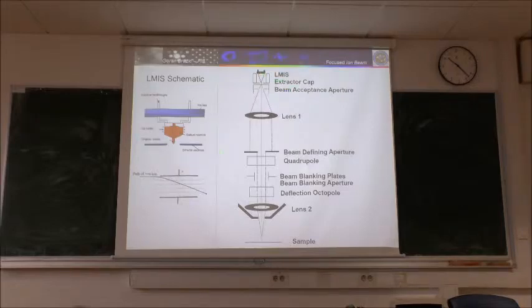this extractor cap. So you extract the ions from that tip. You have a first lens, you have an aperture, you have some quadrupoles and octopoles here. I will explain later on why we do need them. Some blanking plates so that we can blank the beam. We do not want to have a beam, we just blank, we just curve the beam somewhere here. And we have a second lens. The function of the first lens is to make the beam parallel, and the second lens is to make the beam focused. And of course, this focus should be on the center.